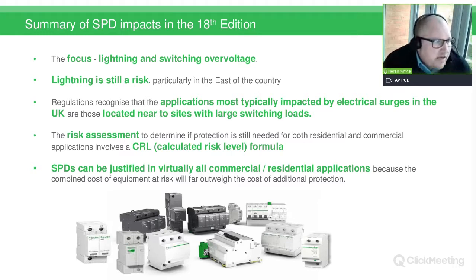So a summary of the SPD impacts on the 18th edition. The focus on lightning and switching overvoltage. Lightning is still a risk, particularly in the east of the country. Regulations recognise the applications most typically impacted by electrical surges in the UK are those located near sites with large switching loads. This would be large industrial estates. The risk assessment to determine if protection is still needed for both residential and commercial applications involves a calculated risk level, and that was the formula we had on the previous page. So SPDs can be justified in virtually all commercial and residential applications because the combined cost of equipment at risk will far outweigh the cost of the additional protection.